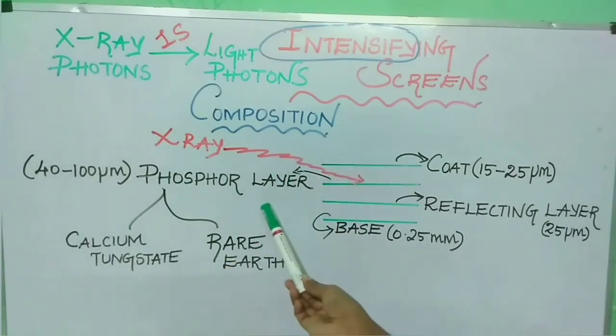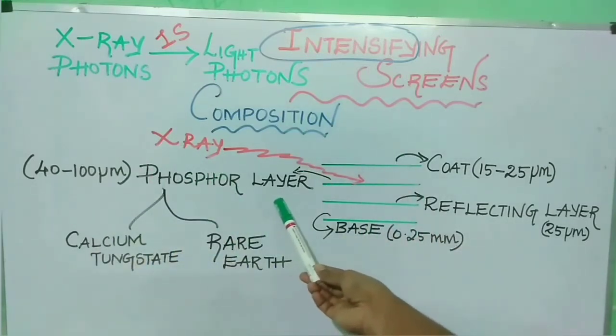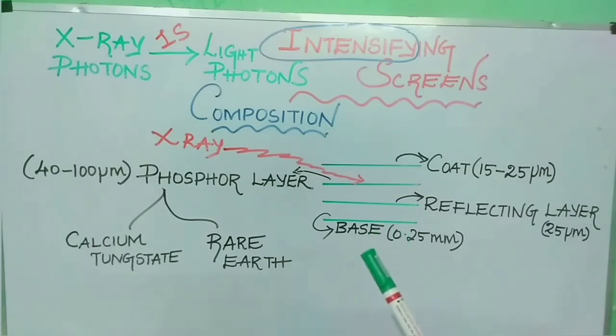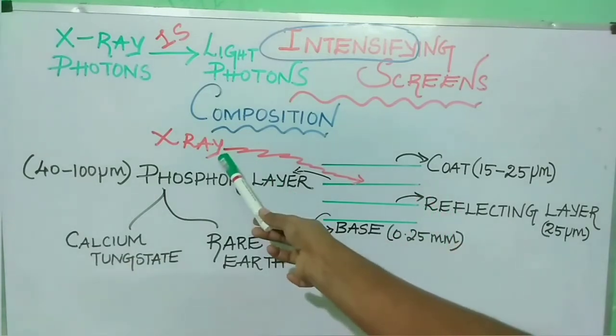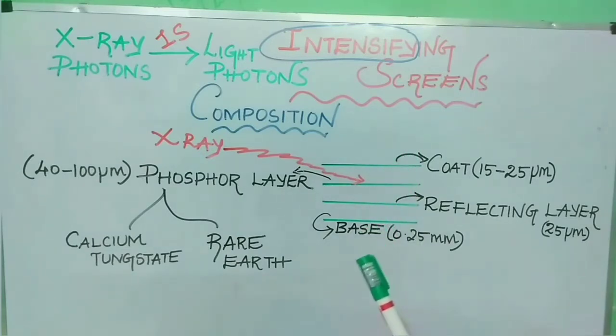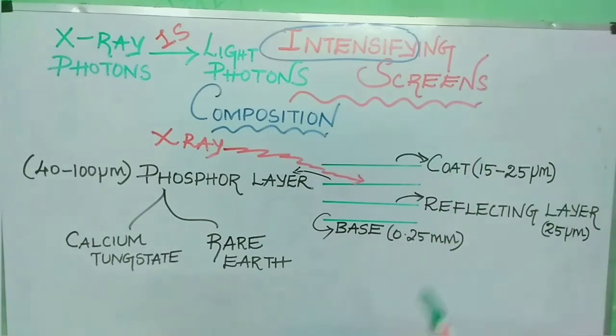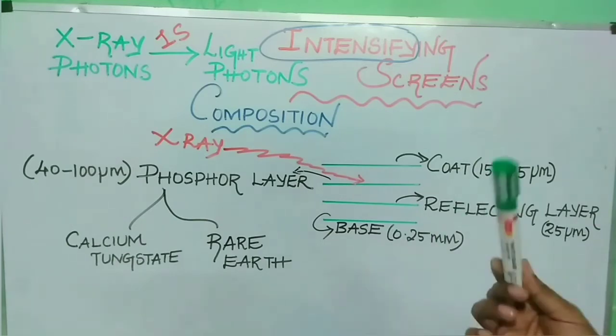Next is phosphor layer. The thickness of phosphor layer is about 40 to 100 micrometers. This phosphor layer comprises phosphor crystals which are suspended in a plastic material. When the phosphor crystals are struck by incoming x-ray photons, these crystals absorb the x-ray energy and re-emit this energy as visible light photons. Even a single x-ray photon absorbed in an intensifying screen generates many light photons, leading to increased film exposure.